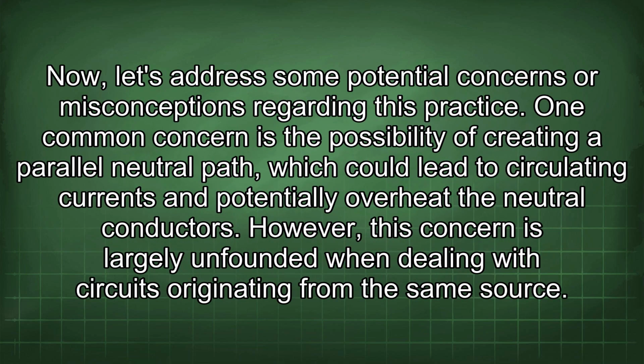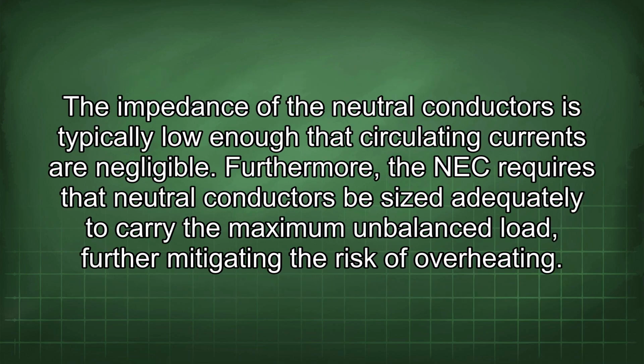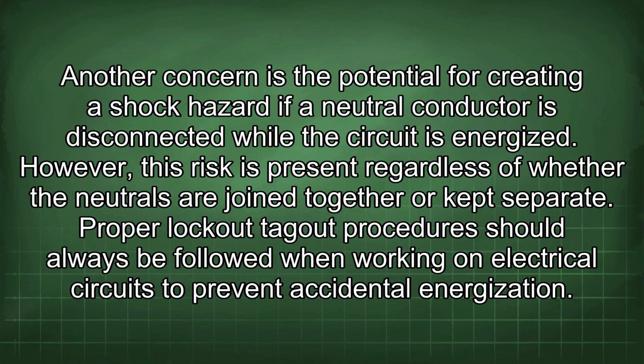Now, let's address some potential concerns or misconceptions regarding this practice. One common concern is the possibility of creating a parallel neutral path, which could lead to circulating currents and potentially overheat the neutral conductors. However, this concern is largely unfounded when dealing with circuits originating from the same source. The impedance of the neutral conductors is typically low enough that circulating currents are negligible. Furthermore, the NEC requires that neutral conductors be sized adequately to carry the maximum unbalanced load, further mitigating the risk of overheating. Another concern is the potential for creating a shock hazard if a neutral conductor is disconnected while the circuit is energized. However, this risk is present regardless of whether the neutrals are joined together or kept separate. Proper lockout-tagout procedures should always be followed when working on electrical circuits to prevent accidental energization.